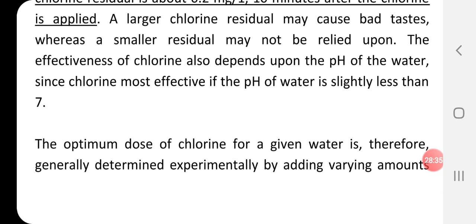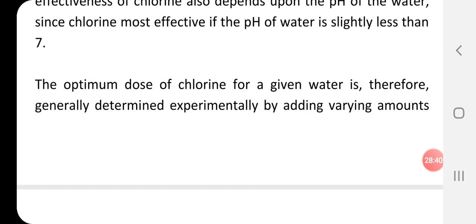Do you understand? The optimum dose of chlorine for a given water is generally determined experimentally by adding varying amounts of chlorine to a given sample. So how is it decided? Different amounts of chlorine are added to the water sample for a period of 10 minutes. Then the dose which leaves a residual of 0.2 milligram per liter is selected.